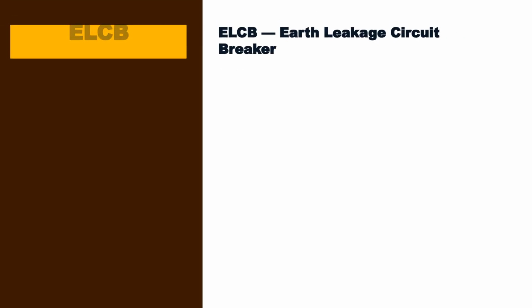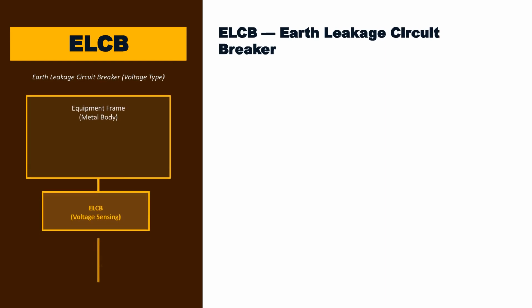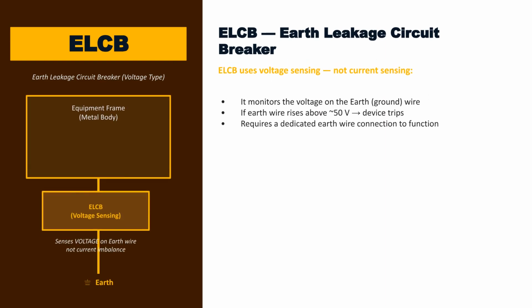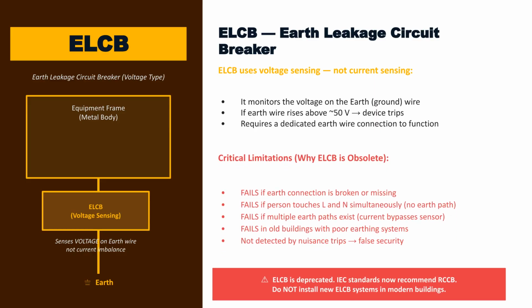The ELCB is an older, obsolete device. It uses voltage sensing, monitoring the voltage rise on the earth wire. ELCBs fail if the earth connection is broken, if a person touches both live and neutral, or if multiple earth paths exist. IEC standards now recommend RCCB, and new ELCB installations are not recommended.